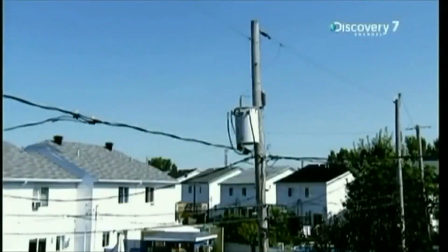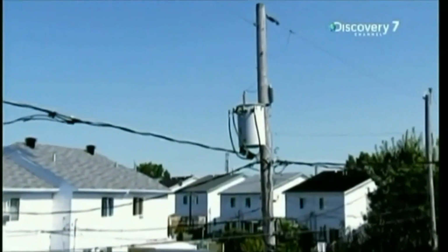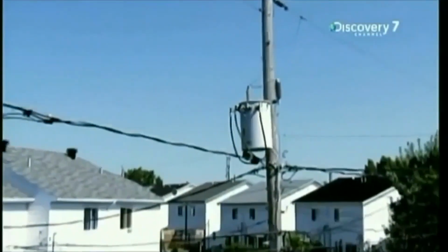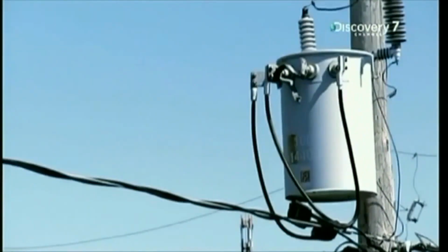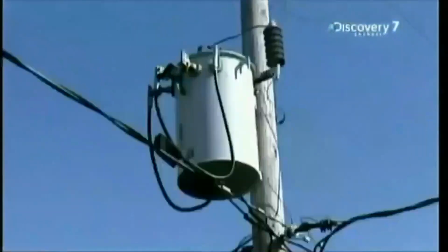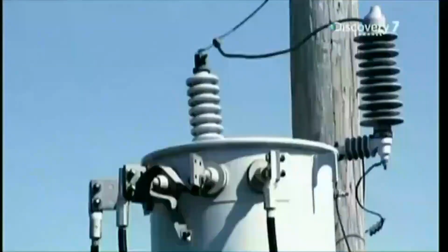There's only one thing left to explain. That constant buzzing. Time to cash in my fancy word coupon. Magnetostriction. It sounds complicated, but it's super simple. It means the metal's vibrating thanks to the alternating magnetic field caused by 25,000 volts. An alternating magnetic field just means its direction keeps reversing itself. With every direction change, the metal bends and regains its shape over and over again. Now you know what all the buzz is about.